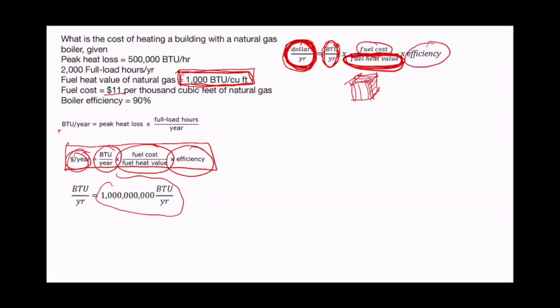Anytime we do combustion, we're going to have exhaust. And anytime we do exhaust, if you've been near an exhaust pipe, it's generally hot. So we're losing some of the heat from the natural gas up the pipe. Now, as an aside, some boilers are much more efficient than others. So in your practice, if you're in a cold climate or a mixed climate, and you have a big building that has a boiler, you should be inquiring to your mechanical engineer about what's called a condensing boiler. A condensing boiler is about 10% more efficient. It'll burn this cubic foot of natural gas about 10% more efficiently.